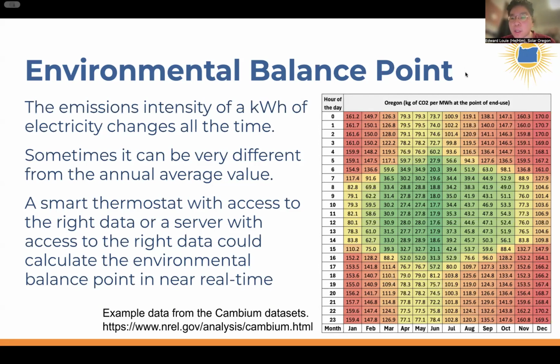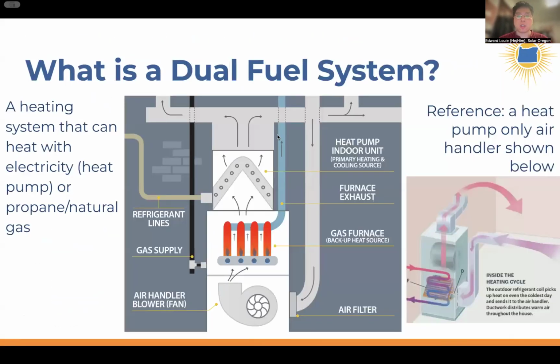Another question is any pros and cons during power outage using generators? Yes. So in a dual fuel system, let's go back to maybe one of the earlier slides to look at a dual fuel system. The only components in a gas furnace that use electricity are this blower, the control board, and maybe a tiny bit of electricity to light up the screen of the thermostat. So it's relatively little electricity for a generator to support a gas furnace during a power outage.